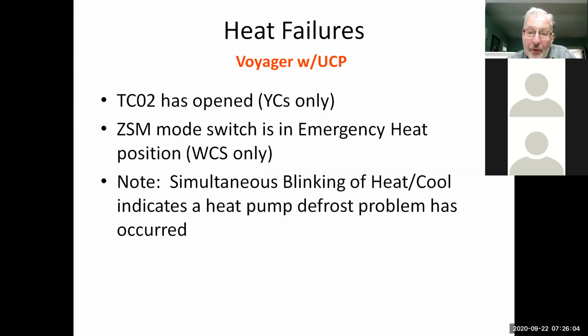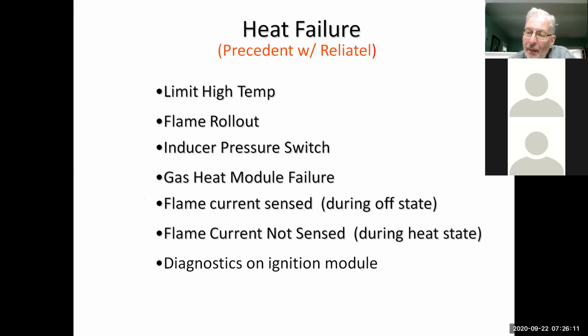You may have a zone sensor module if you have a heat pump. But usually it's a high limit trip, and if it trips 3 times on a call, it may go into a heat fail. If it's a flame rollout, it'll go into a heat fail. If your inducer pressure switch doesn't make, gas heat module failure, flame current sensed in the off state, flame current not sensed, but there are diagnostics on the ignition module. But typically in a heat fail, in my experience, 99% of the time, it's tripping the limit. And it could be loose belts, could be dirty filters, could be a plugged evaporator, it could be anything, you know, but it's typically a limit switch at that point.